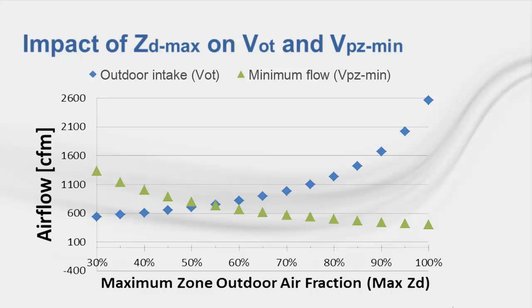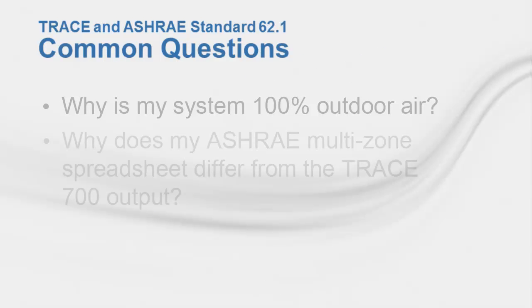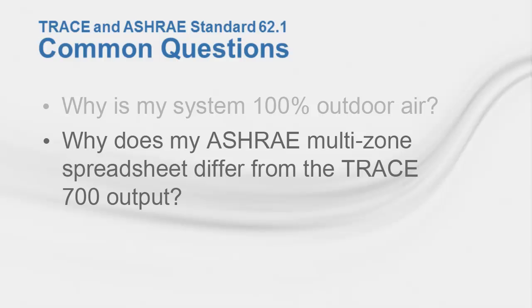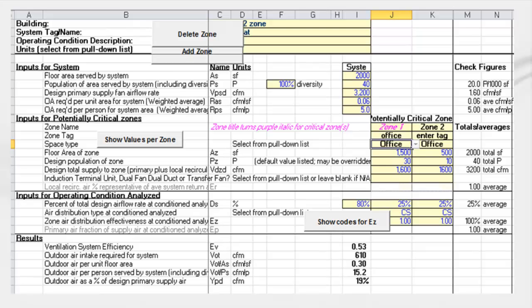The next common concern is why the ASHRAE multi-zone spreadsheet does not match the TRACE 700 output. When using the ASHRAE spreadsheet, the key inputs likely causing the discrepancy are the percent of total design air flow rates at conditioned analysis inputs, also known as the D sub S variable. The system D sub S represents the system diversity percentage, and the zone D sub S values represent the zone minimum stop percentages.